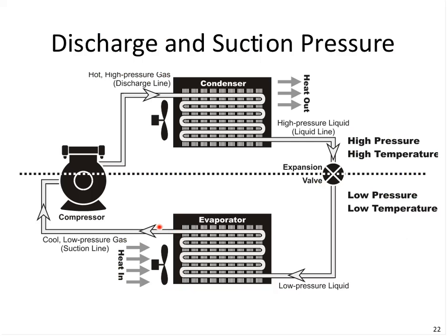In larger industrial systems, sometimes we just flood the evaporator with liquid, and there's a recirculating tank here that just keeps the liquid in the evaporator and not going to the compressor. So when we talk about resetting the suction pressure here, it's essentially causing the compressor to unload sooner than keeping the compressor loaded essentially down to whatever temperature that we desire.